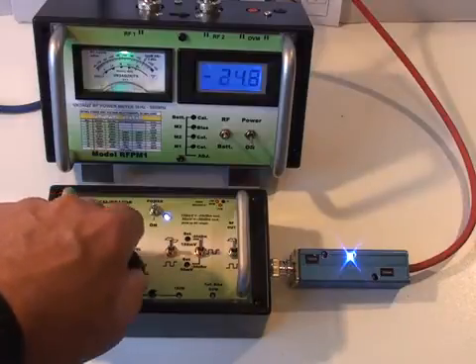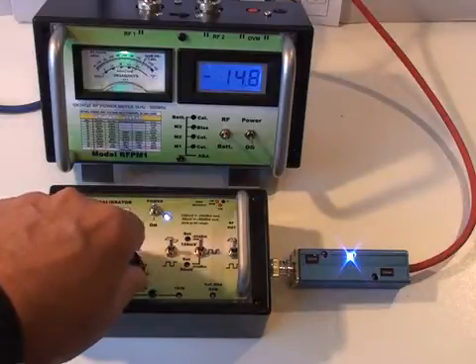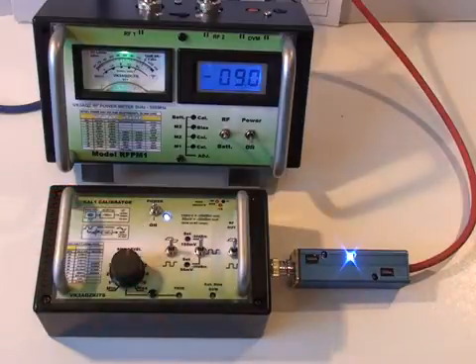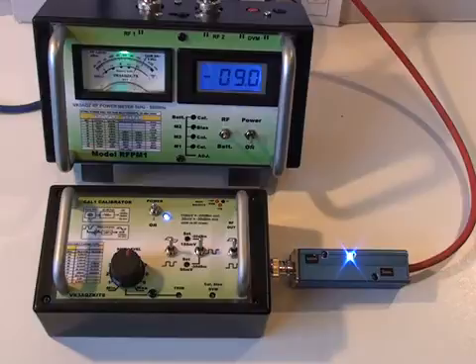And the range of adjustments from around plus 10 to 13 dBm down to around minus 40 dBm. And you can use this sine wave through a series of switched attenuators to measure your overall linearity of the power meter. You have to use a sine wave and that sine wave has to be very clean.